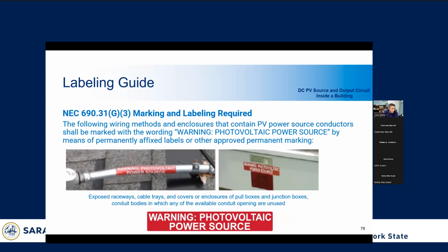Here's what I was talking about earlier with the DC power going through the conduit. You have to make sure that all DC conductors are in metallic raceways or metal clad cable inside a building. They also have to have this labeling, which is the PV power source warning label at a minimum of every 10 feet. And that's when it's DC conductors. Many people don't like the look of this, which is understandable, so a lot of times they'll run the conduit through their attic space or use microinverters to avoid having to see that, because if you use microinverters, it changes to AC right at the panel, and then you don't need this label.